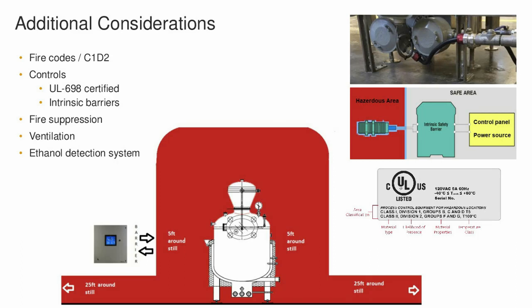So if you're in a C1D2 environment, what a lot of people call that red area that I have around the still, they call it, it's pretty harsh, the sombrero of death. What that means is around your distillation equipment, there's an area that if there's a leak, that's where those vapors are going to be. So 5 foot around the still, from any point of that still, that's where vapors could be leaking out, coming out of the still.